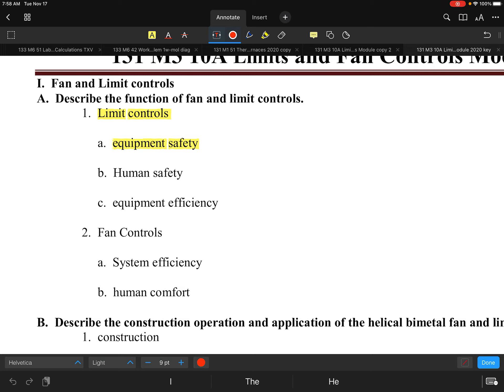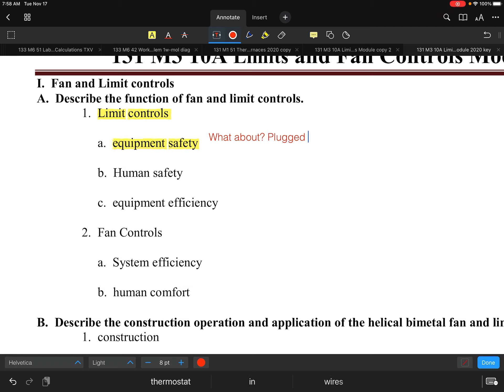Related to equipment safety, the big thing to think about is limiting the heat exchanger temperature. Some of the most common issues we can run into are plugged filters on a job. Whenever there's an airflow problem — somebody has a restricted filter or even an undersized filter — that's a major problem.